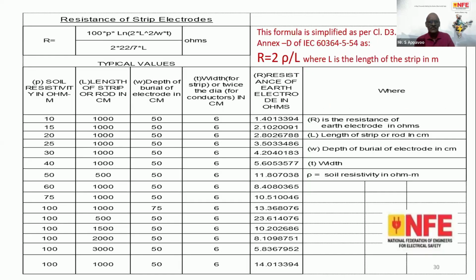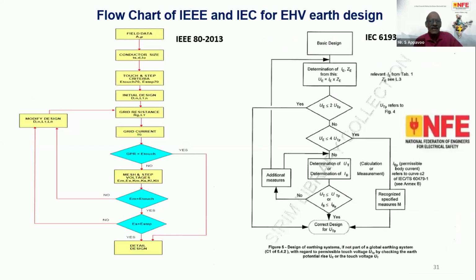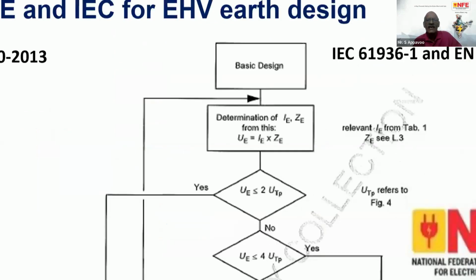calculations. This is sufficient. Finally, at the end of the day, we are going to validate the results by testing only. During testing, there is not much difference between the adoption of this formula and the simpler formula. And that's why the chart also specifies the difference between the IEEE and IEC. There's no doubt that IEEE has paved the way for the creation of so many concepts by the IEC itself. But it can be used for the initial design; for transparency and stringent as well as confident measures, you can go for the IEC one.